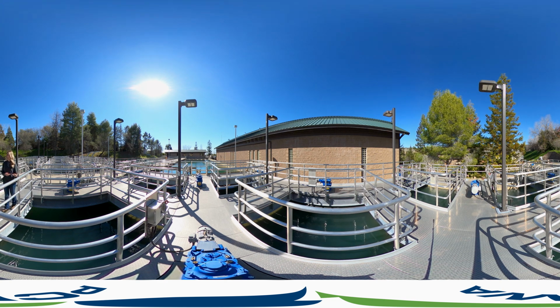I'm going to discuss the flow of water on how it goes through the flocculation basins. As it comes from the rapid mix, it's going to enter this first chamber. It's going to go underneath the baffle wall that you cannot see into this next chamber. It's going to go over this next baffle wall into the last chamber, which is also the slowest mixing speed. This last baffle wall before the sedimentation basin has perforated holes that evenly distribute the water into the sedimentation basin. And let's go talk about that process.